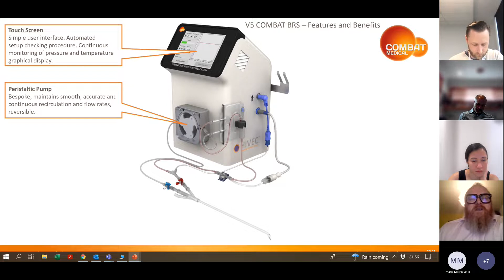A peristaltic pump, a nice, clever pump. If it feels a blockage, it stops and reverses. This allows the nurse to leave the patient alone for an hour. We will generally leave the patient with a buzzer or just with the ability to shout for the nurse, but they don't need sitting and watching for an hour. Temperature probe, although we're measuring the temperature here, the temperature we're showing on the screen is that of the bladder.